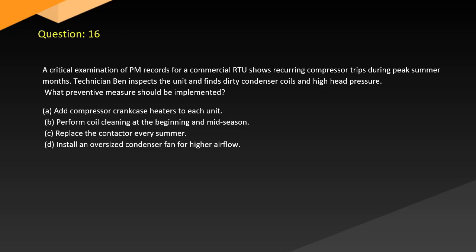Question 16. A critical examination of PM records for a commercial RTU shows recurring compressor trips during peak summer months. Technician Ben inspects the unit and finds dirty condenser coils and high head pressure. What preventive measure should be implemented?